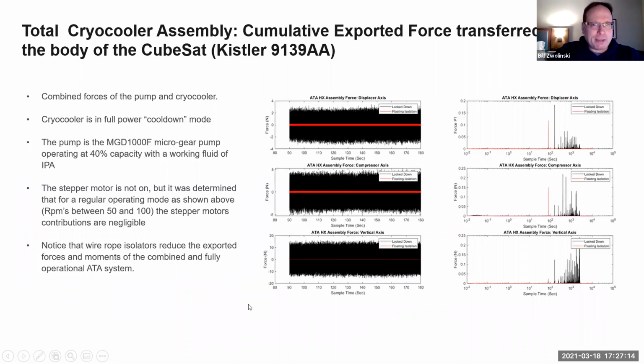Some results, and again, these are preliminary results, the testing is still going on. Basically the black section is when you have everything locked down, everything hard mounted, and the red section is when you have it on these wire rope or passive isolators. And what you see there is that the passive isolators actually bring the vibration level down substantially. And this is really the total cryocooler assembly, underneath the cryocooler assembly. So very successful, I think. The passive isolation did quite a good job in this case.